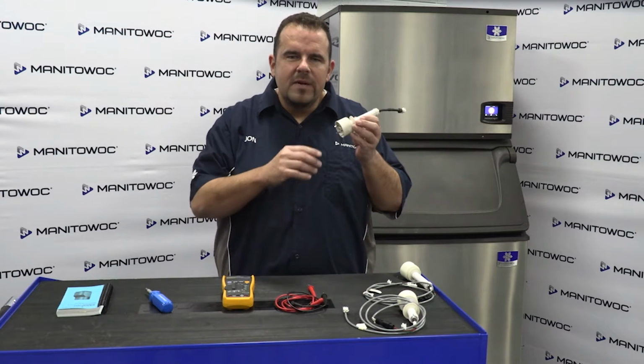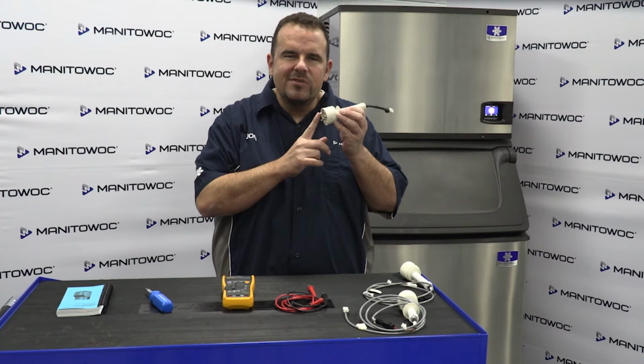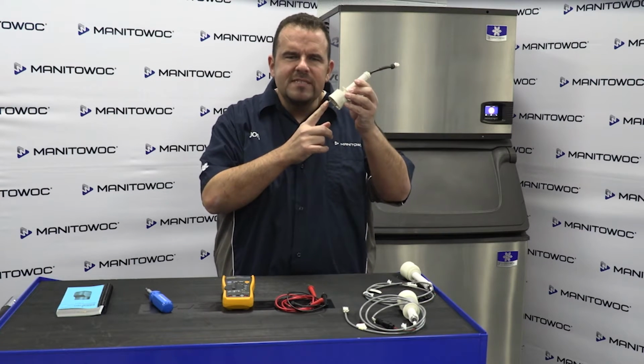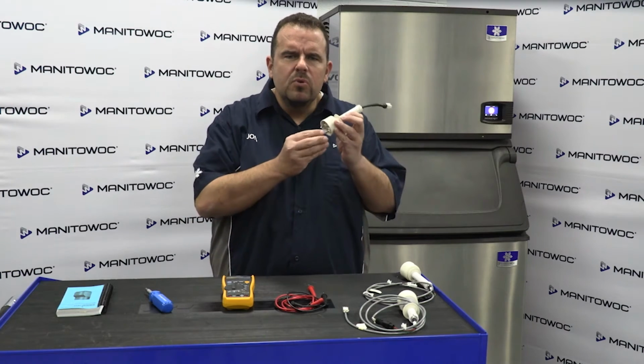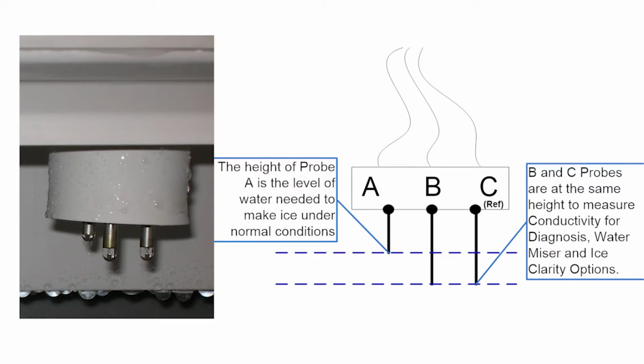In this video, we'll be covering the Indigo NXT water level probe troubleshooting. The water level probe controls the water level by sensing whether the water is or is not contacting the water level probe. There are 3 sensing probes. 2 probes are equal in length, and they're used to measure conductivity for diagnostics, ice clarity, and reverse osmosis options. When in the default or factory setting, the resistance level is taken between the 2 long probes and continues to fill to the short probe.